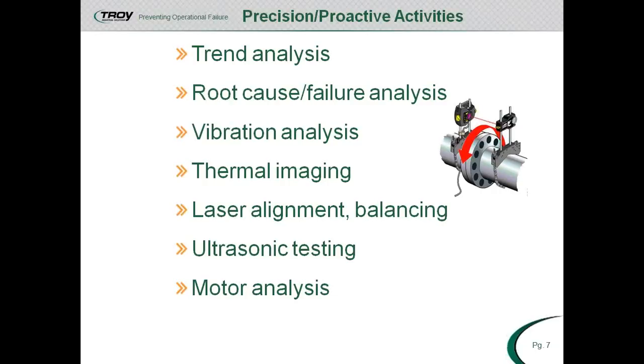The two remaining fault zones are the rotor and the stator, and this software actually goes out and checks the rotor and the stator for the proper integrity of the rotor bars, the rotor laminations, the end rings, the squirrel cage, and so on. And in the stator fault zone, it allows early detection and prevention of motor failure surrounding the stator windings. Stator windings are the heart of the motor, producing the rotating magnetic field, the induction current, and the torque to turn the motor and the rotor shaft.